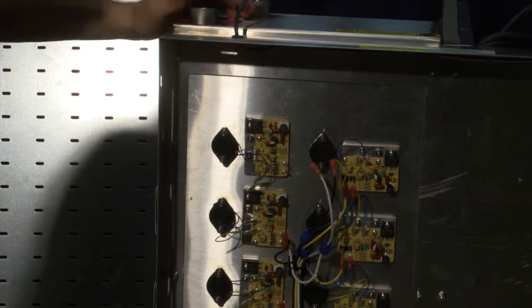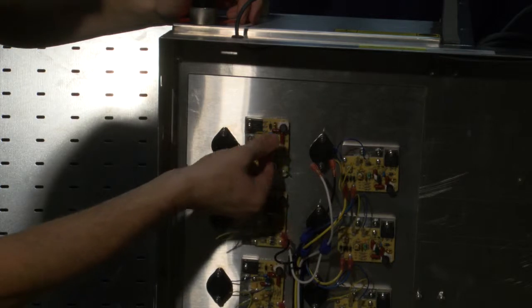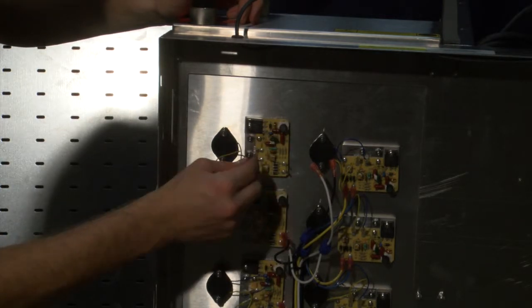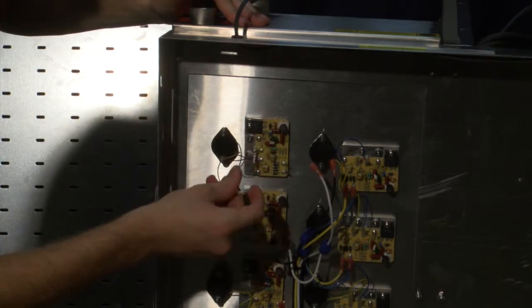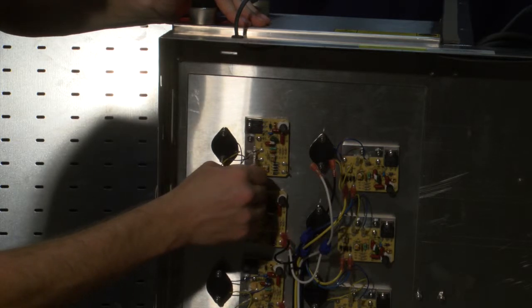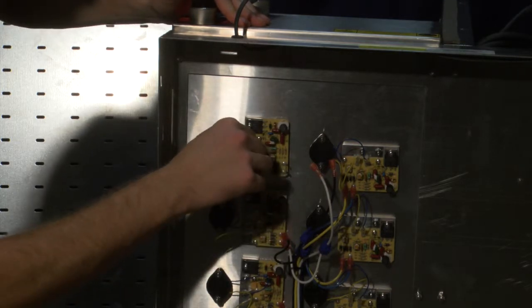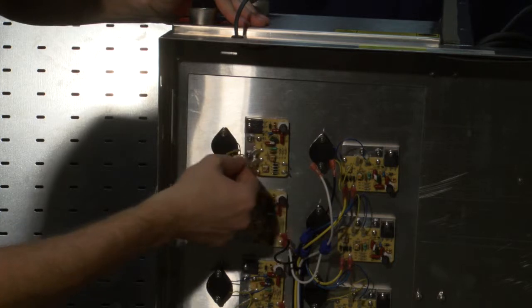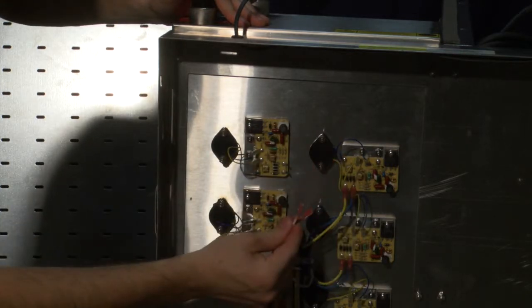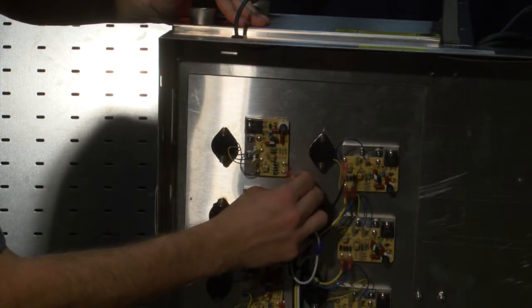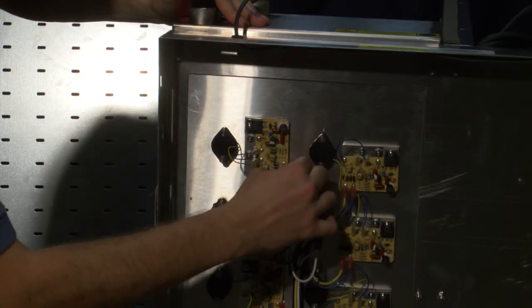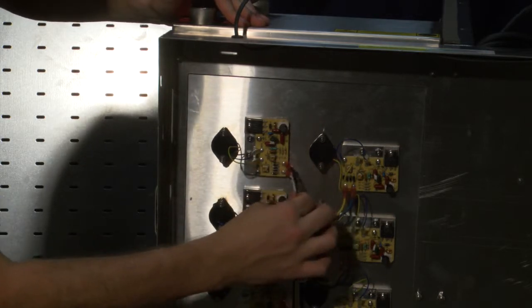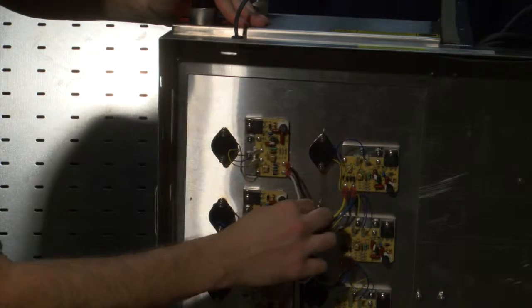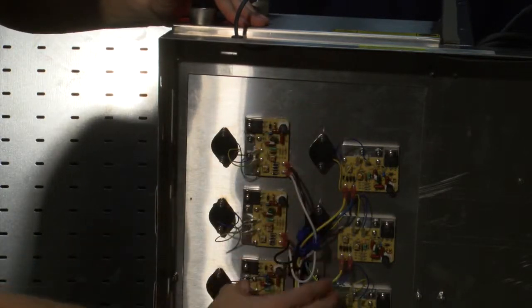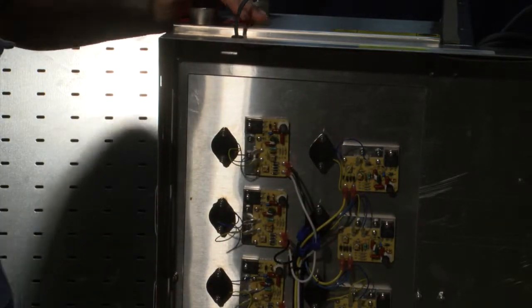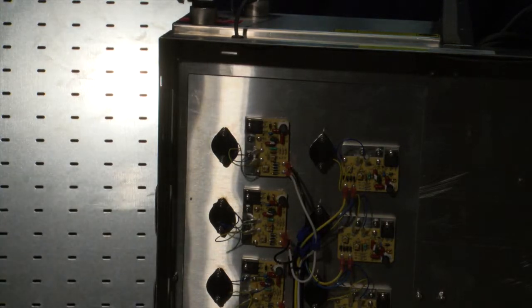After the circuit board and transducer are reinstalled, make sure you plug the transducer into its circuit board per instruction. Yellow on pin 1 and blue on pin 2. Also make sure you reattach your daisy chain lines per instruction. White on number 1, black on number 2. After reinstalling all your transducers, double check all your electrical connections are tight and secure before reassembling the mist-free.